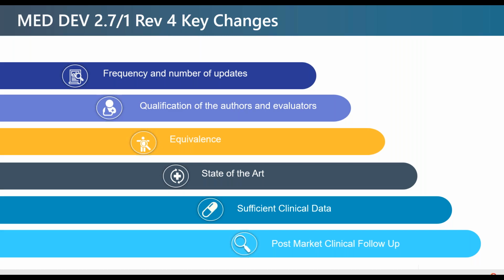But I have seen questions from the notified bodies stating that the author who had a PhD in biological engineering was not a qualified author, and that a physician with a different specialty was not a qualified reviewer. So make sure you have all those boxes checked on your report.